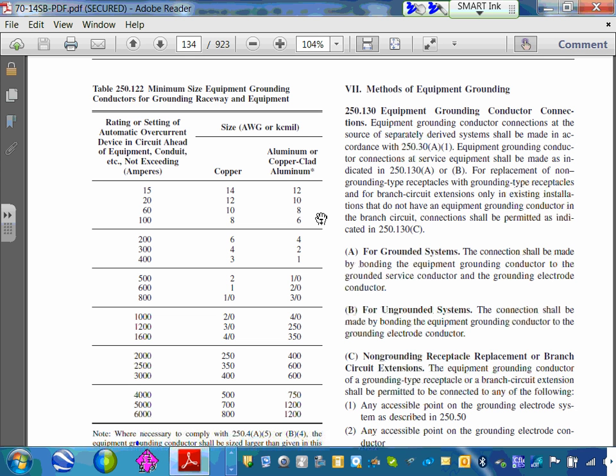The ground. Now, if you're putting it in a PVC, you need the green conductor. If you're putting it in an EMT conduit, you don't need the green conductor because the conduit itself will act as a green conductor. The technical term for it is equipment grounding conductor. That's why the frame of that lighting fixture, you tie the frame to this wire. So if Chad is changing the ballast there, and accidentally you don't put this wire, this is only for safety. The ground is for safety.